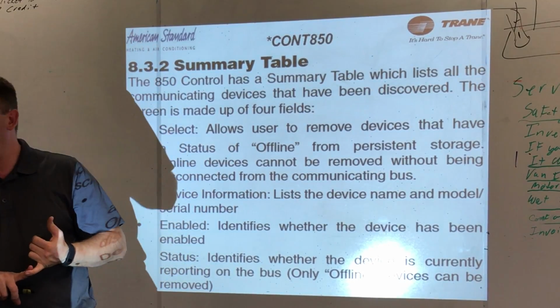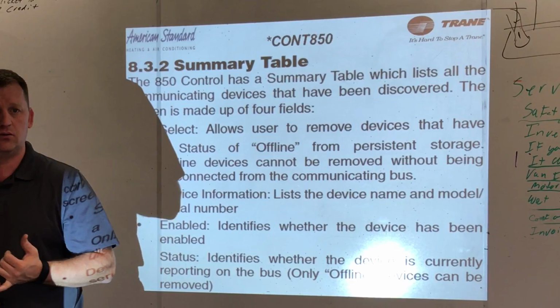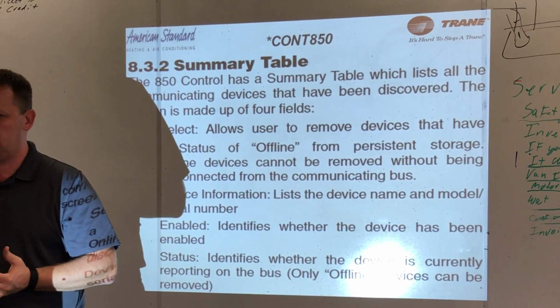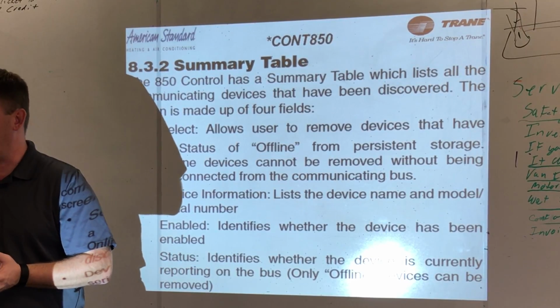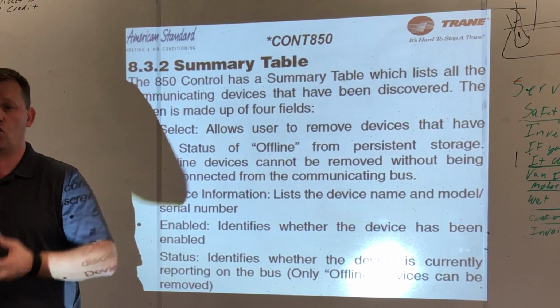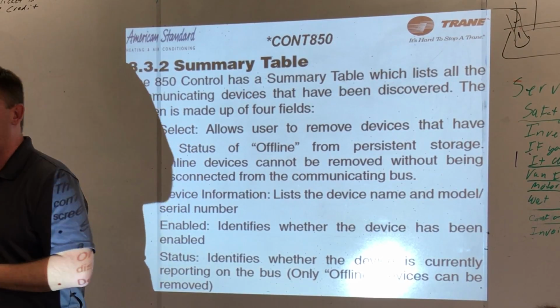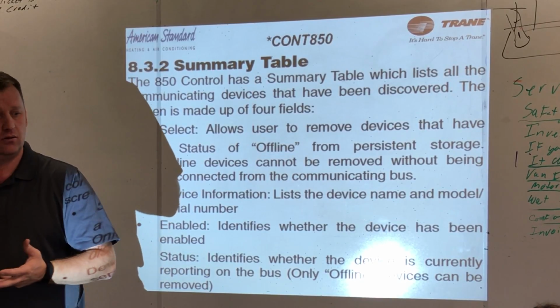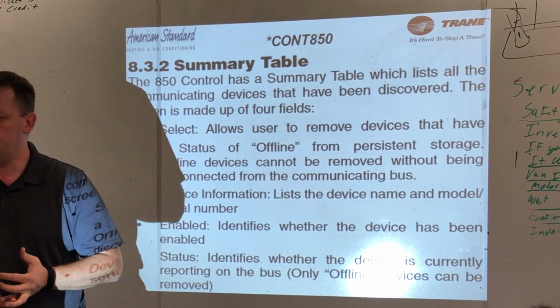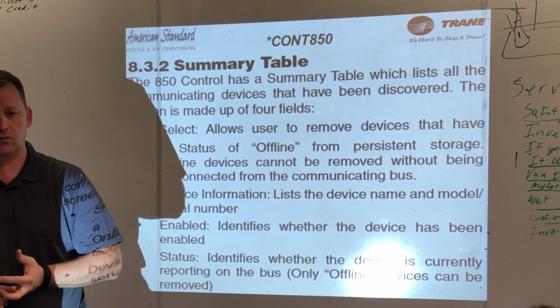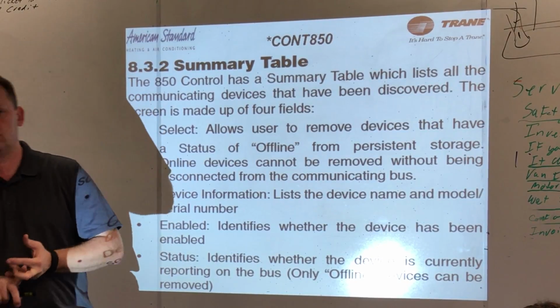Remember, 13 volts DC is good communication. 16 is open. We have a broken wire somewhere. 0 volts is a short. Okay, a short brings down the whole communicating system, by the way. So everything would show offline. What were those again, Aaron? 13 is good. 16 is an open. 0 is a short. So open, you mean is not calling? It's a broken wire.